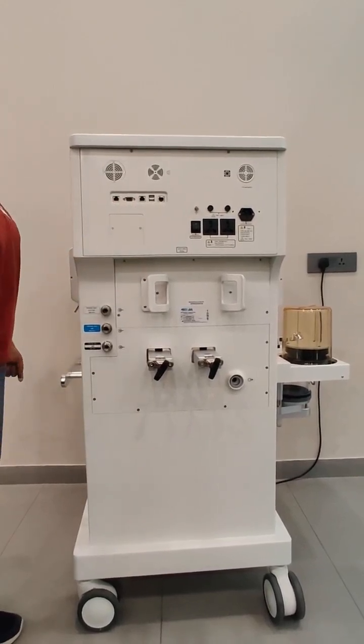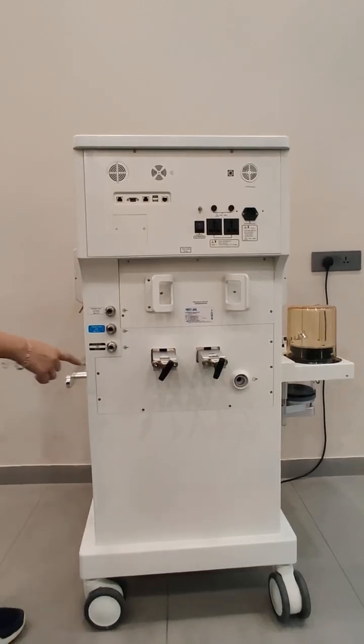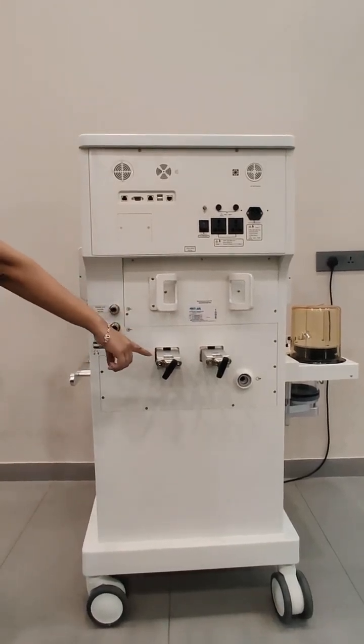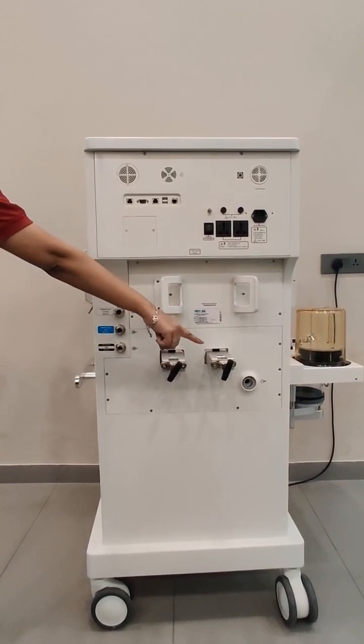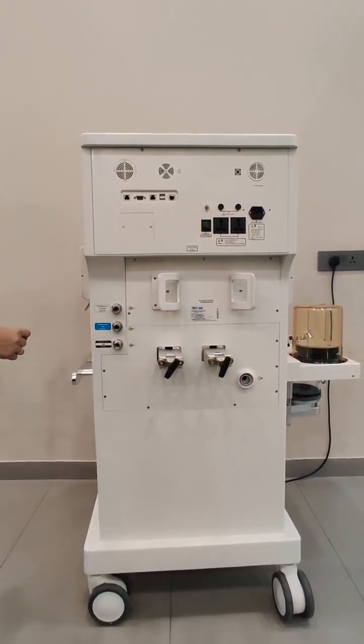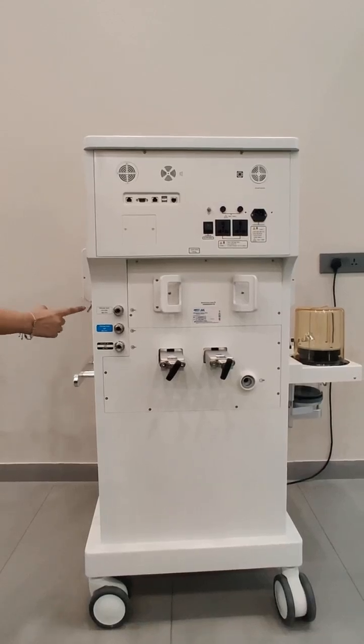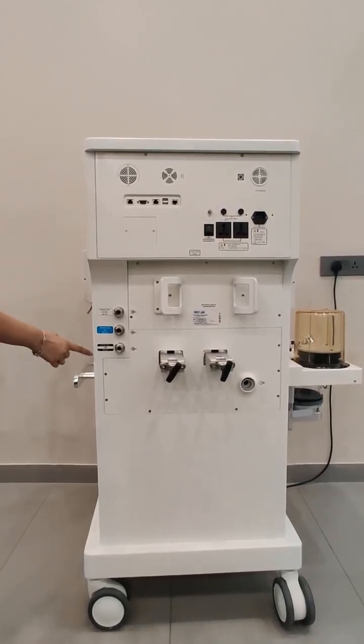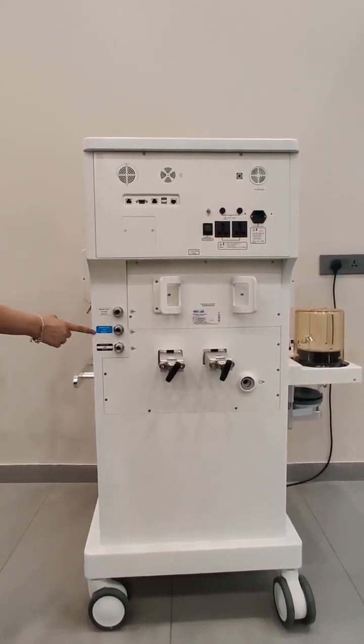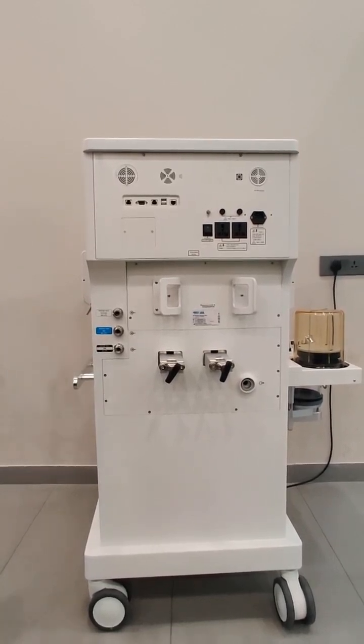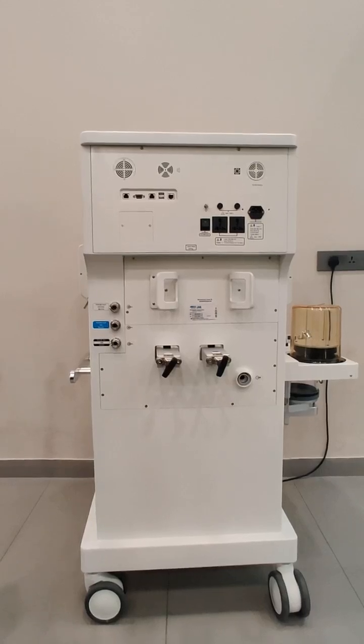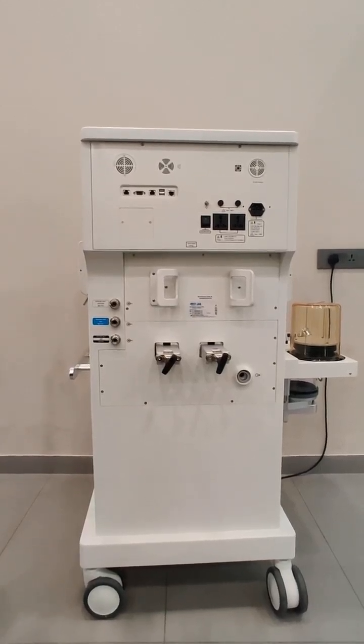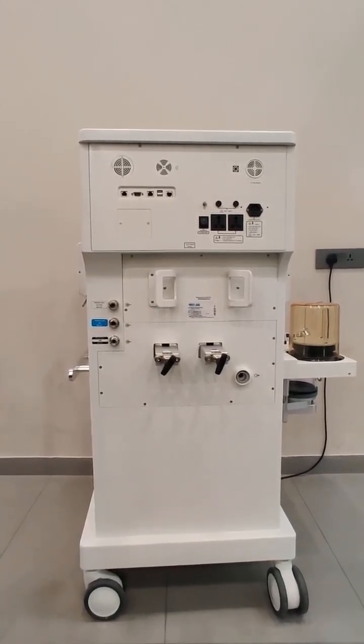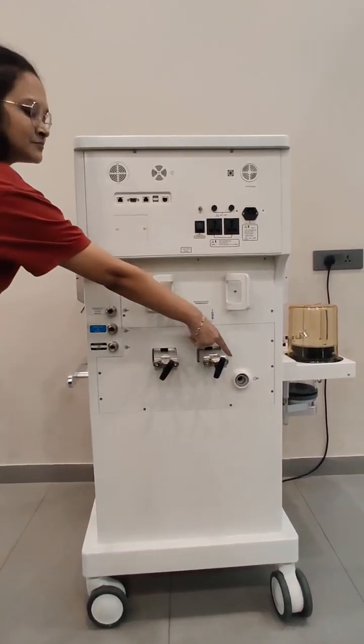Then at the back side itself we have the yokes. One is for oxygen, where you can mount the pin index cylinders, and the other is for the nitrous oxide cylinder. Then dedicated connectors are there for the pipeline system: for the oxygen, for the nitrous oxide, and for the air. And at the back side itself we are giving the scavenging port, where you can connect either the passive scavenging system or the active scavenging system. So this is the port over here.